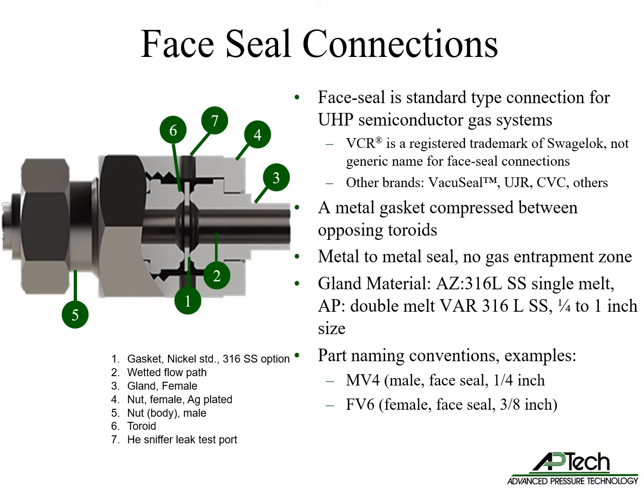The most common connection in semiconductor gas systems is the face seal connection. While sometimes generically called VCR connections, VCR is a registered trademark of Swagelok and not a generic name for face seal connections. Other face seal brands include Parker's VacuSeal, Fujikin UJR, KITS CVC connection, and others. The face seal connection uses a nickel or stainless steel gasket compressed between two opposing toroids to affect a metal-to-metal seal with no gas entrapment zones. APTEC uses single melt 316L stainless steel for the AZ product series glands and double melt 316L stainless steel for the AP series product glands.